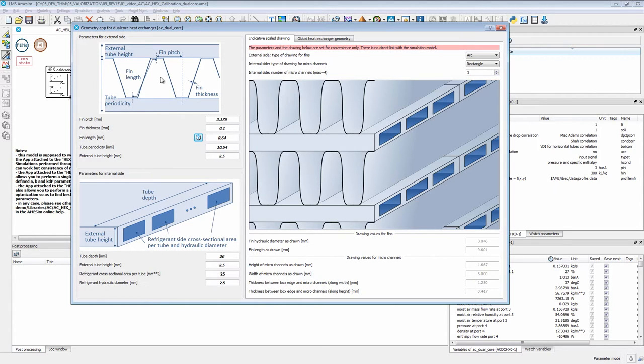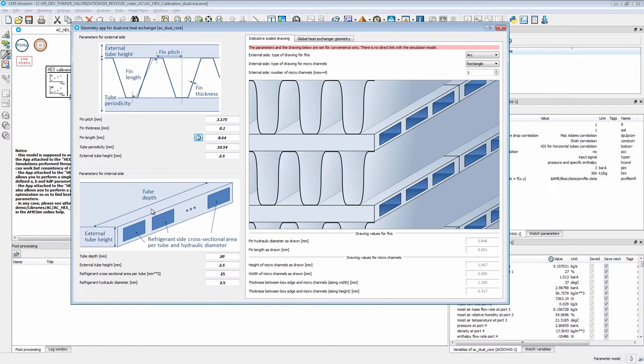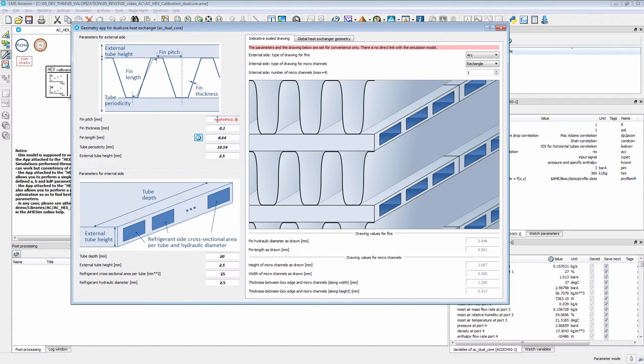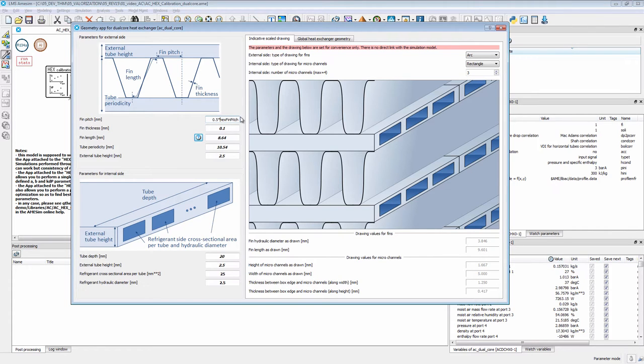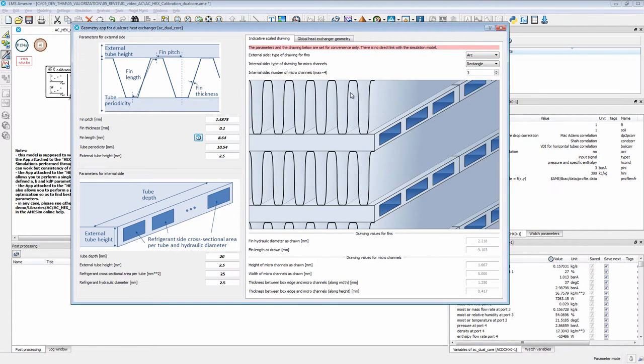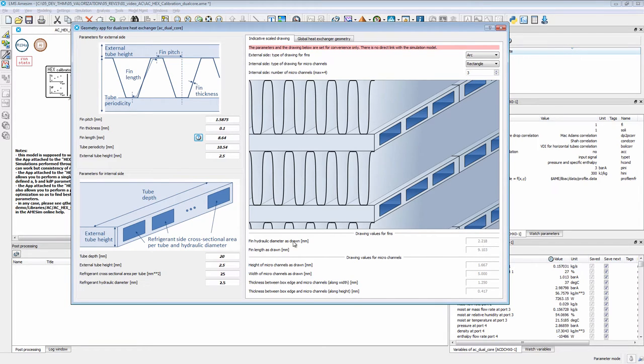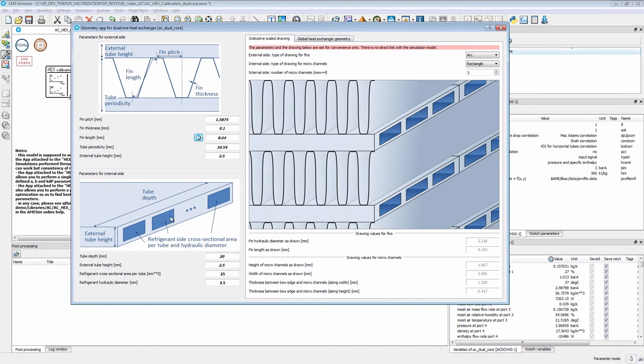Here you have parameters for the external side, that means where the air flows through fins, and here are parameters for the internal side, the refrigerant. For instance, consider you want to half the fin pitch, that is the distance between fins. You can see that the drawing automatically adapts. The second thing is that there are some post-process values here such as the hydraulic diameters or the fin lengths and so on.